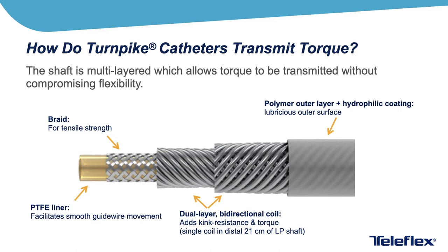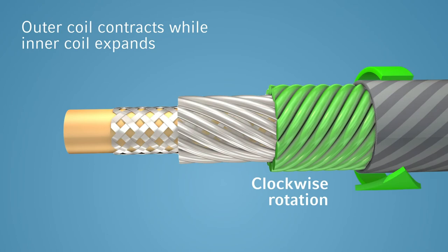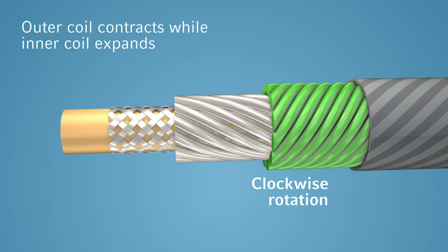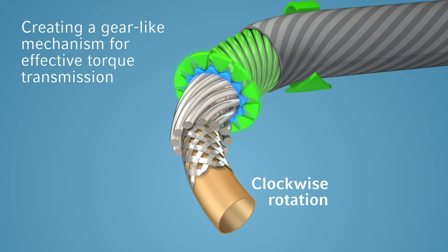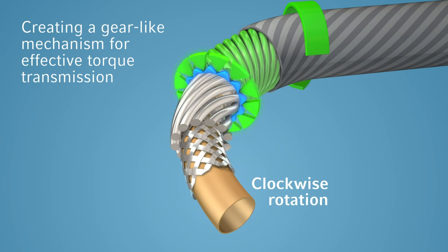Specifically for the Turnpike product, this unique feature of how coils transmit torque - by either expanding or contracting until they hit a limit - is the driving factor behind the design of that device using a dual layer coil instead of a single layer coil. When you torque that catheter in the clockwise direction, the inner coil actually expands out and the outer coil contracts down. That's what contributes to the torqueability of the catheter while still allowing it to maintain the flexibility you need to navigate through tortuosity and reach the lesions you're treating.